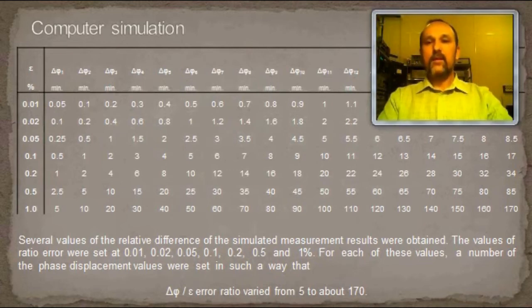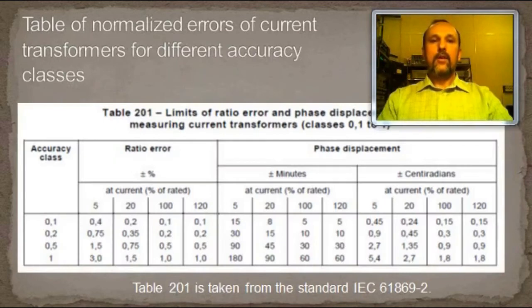It should be noted that for a rated current of 1A that is 100% in the table, the value of the phase displacement should not exceed 30 minutes for class 0.5. However, for the rated current of 5A, the ratios analyzed in the work and presented in the table correspond to 20% of the rated current. I remind you, the calculation was performed at a current of 1A.